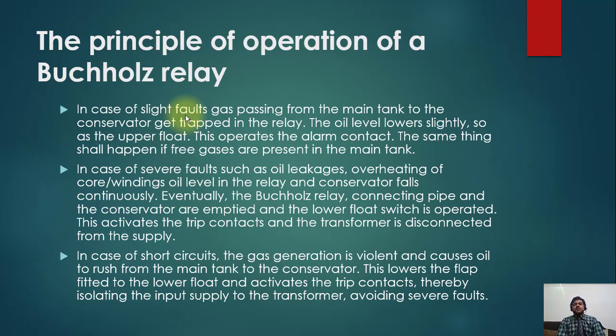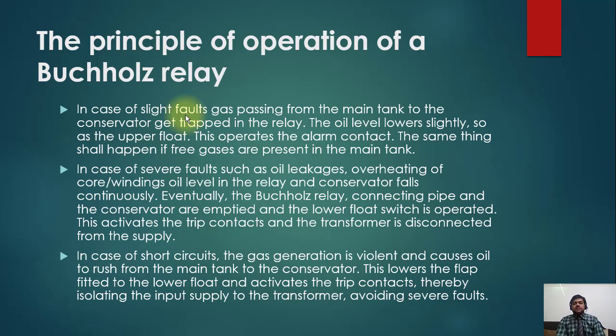If the transformer has been in service for a long time and the Buchholz operates, you need to investigate the reason. In the case of severe faults — such as oil leakage or overheating of the core and windings — the oil level in the relay and conservator falls continuously. Eventually the Buchholz relay's connecting pipe and conservator are emptied, and the lower float operates, activating the trip contact and disconnecting the transformer from the supply.